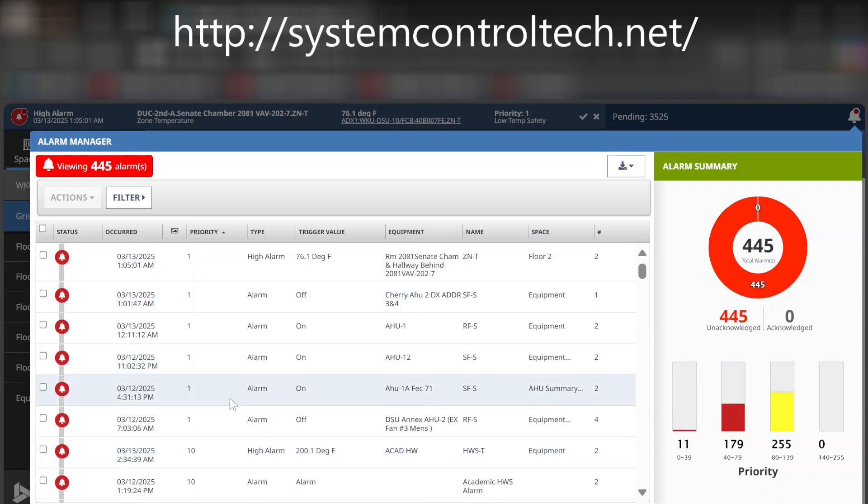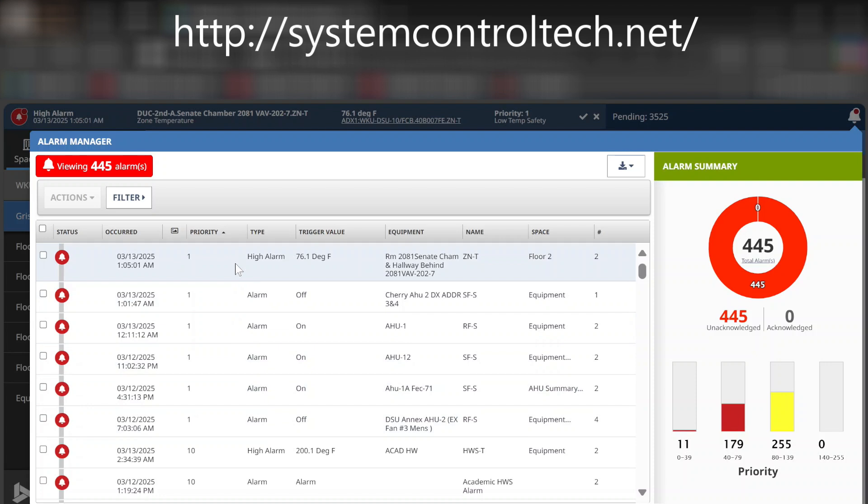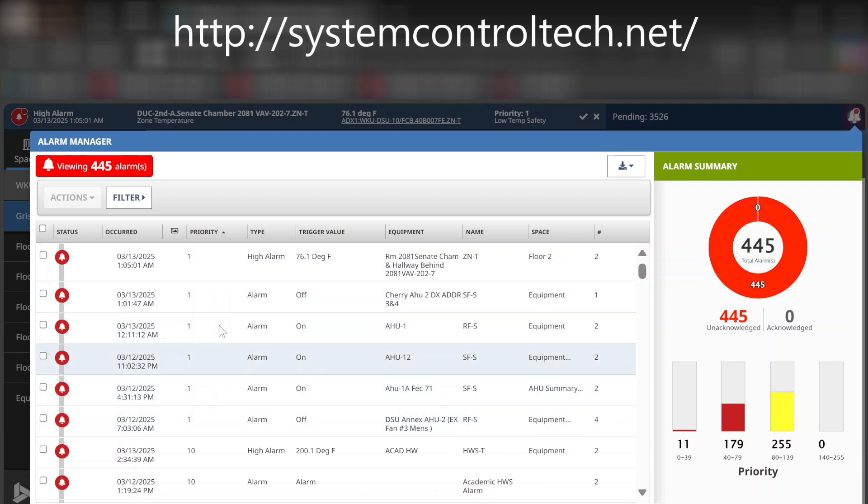Just the way that we use this is something that requires someone to physically go out and reset something. We set those as a priority level of one. That way, when we come in of a morning or whatever, we can simply hit the alarm dashboard, sort through priorities, and then we can go through and dispatch whatever we need done to send technicians out to resolve the issues.